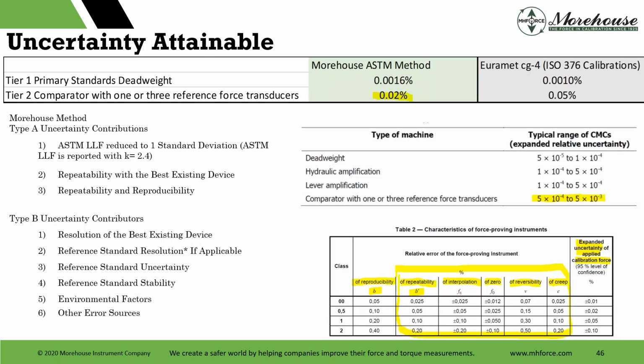Now, I said something about ISO 376 earlier, and here's just one slide comparing this. If attainable, with the Morehouse ASTM method, we're basically at 0.0016%. That's what we start at, particularly for our standards. And what's attainable with 1 or 3 reference force transducers is about 0.02%. ISO adds a lot more criteria like interpolation, percent zero reversibility, and they even add creep in there, and therefore that jumps to about 0.05%. So just a slide to show what ISO 376 adds as far as things go that we're not getting with some of ASTM. We're not getting usually reversibility and creep and some other things.